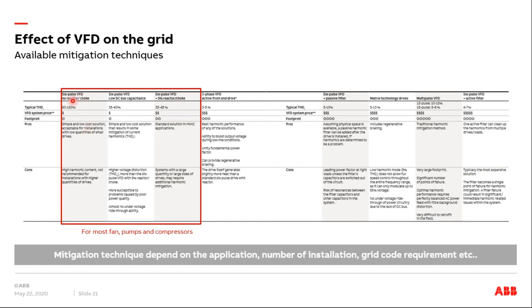In the first column, what you see is the 6-pulse VFD, and if you use no mitigation techniques, just the diode rectifier only, then your typical harmonics is like 90 to 120%. So it's a pretty high harmonic content. It's not really recommended, but if you're using just one drive, let's say a 7.5 kilowatt drive on one of your motors, I don't think it matters a lot, because you could use it even without anything. Even by standards, if you are below 7.5 kilowatts of power rating, at least here in the US and also in Europe, you are not required to put any mitigation on that drive. So it's up to the customer if they want to do it or not.